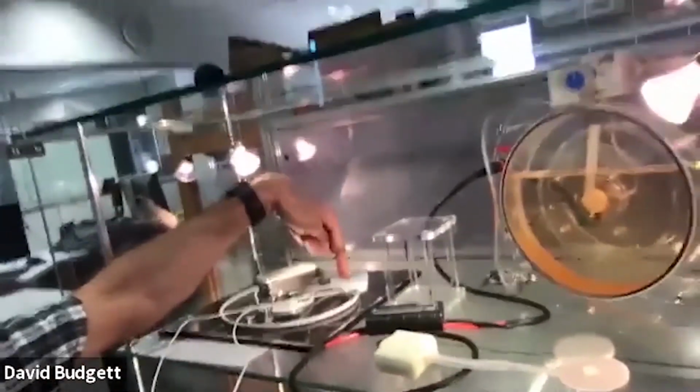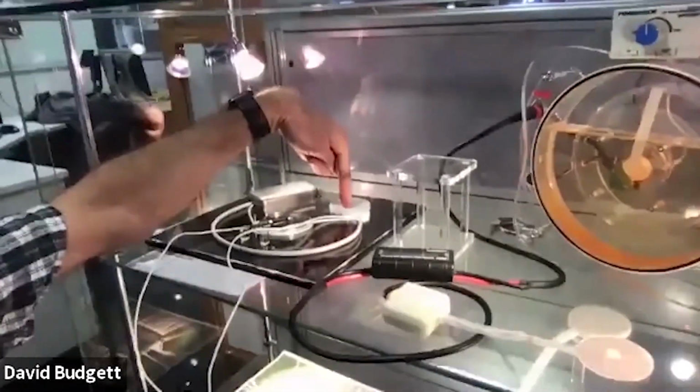Alongside that pump, you can see here we've got our coil, which is their charging coil to provide it with power, and that's a power pack, which does include a small battery, enough to run the pump for about half an hour, so the person can have a rest from having their charging coil on. They can go and have a shower, that sort of thing, or if it falls off, they've got time to put it back on again. We can't stop these pumps. Once you've started them running, you've got to keep them running, because if they stop and they get clots in them, you can't turn them back on again because you can't have those clots being pushed into the body.